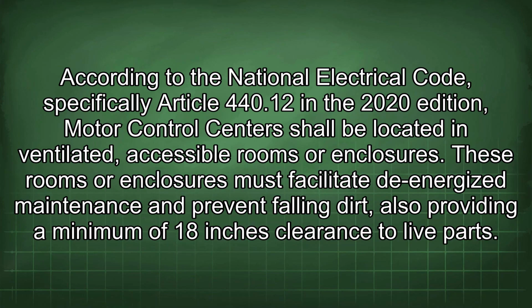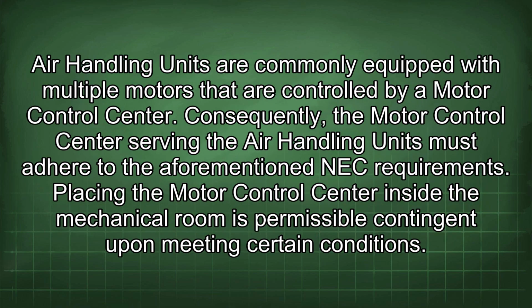According to the National Electrical Code, specifically Article 440.12 in the 2020 edition, motor control centers shall be located in ventilated, accessible rooms or enclosures. These rooms or enclosures must facilitate de-energized maintenance and prevent falling dirt, also providing a minimum of 18 inches clearance to live parts. Air handling units are commonly equipped with multiple motors that are controlled by a motor control center. Consequently, the motor control center serving the air handling units must adhere to the aforementioned NEC requirements.